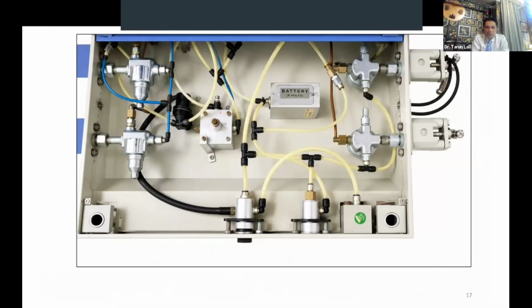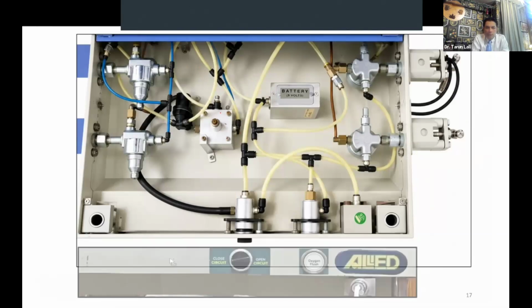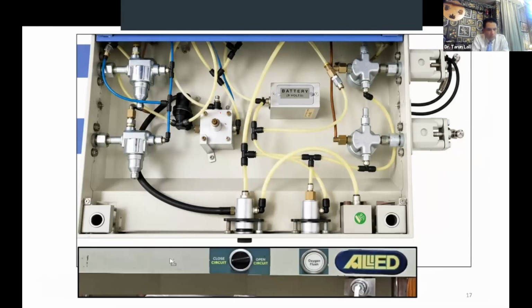Now I will show you once again how this corresponds to what we see on the outside. Looking from the outside, here is the common gas outlet, where we also have the closed circuit or open circuit selector switch. That is just your distribution. From here, the gases go either to the common gas outlet or to the closed circuit. This black tubing you must remember, because we will cover it once again when we come to the closed circuit. So here you have the closed versus open circuit selector switch, and this, as we covered, is your oxygen flush, and then the common gas outlet. From the outside, it will look like this.